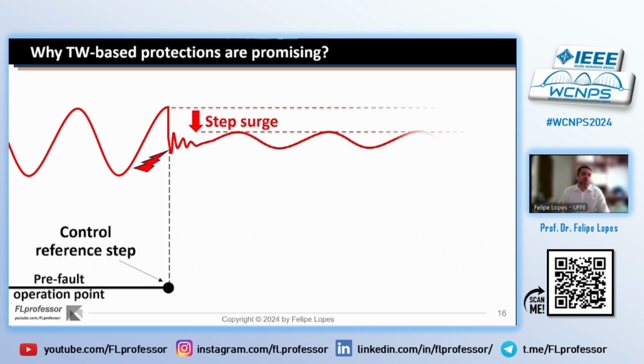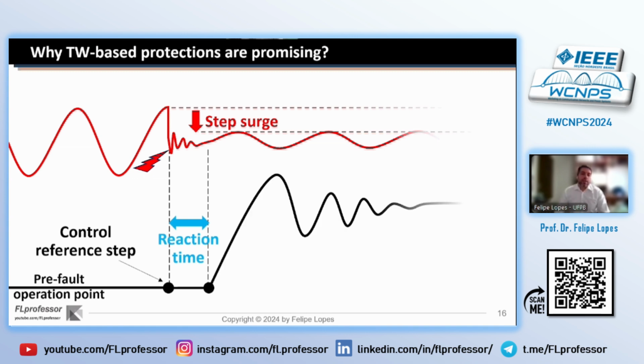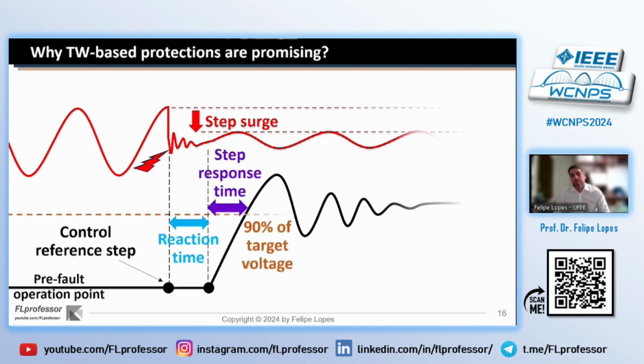But from the perspective of the controllers applied in the IBR, after the fault, a control reference step will be seen. There will exist a reaction time, and then the controllers start to act, trying to move the quantities to another point of operation. We know that there is a step response time within which most protection functions will try to take decisions, and I mean most conventional protection functions. And this is a problem because the controllers are still trying to converge to their final values.